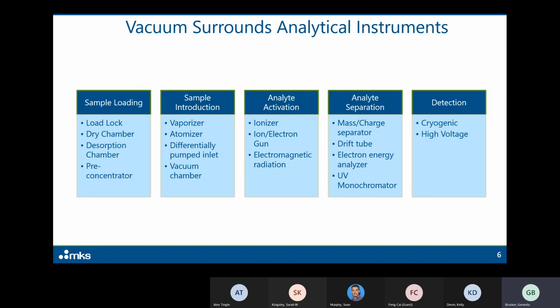From the sample loading, typically, you then go into the sample introduction building block, where we introduce the sample into the instrument, and that could be a vaporizer, an atomizer, maybe a differentially pumped inlet system, or maybe that's the vacuum chamber of the vacuum system itself. But in any case, vacuum is required again for the vaporizer, right? Or for the atomizer, I have to pull on a liquid, right?